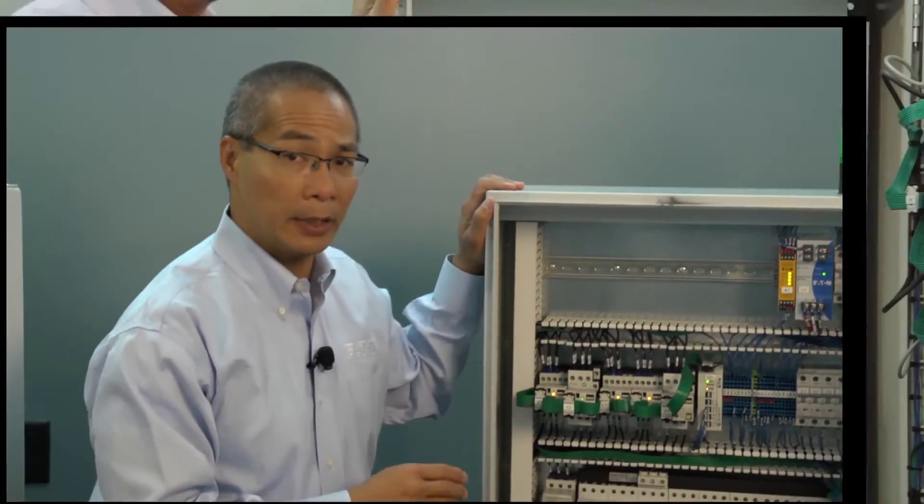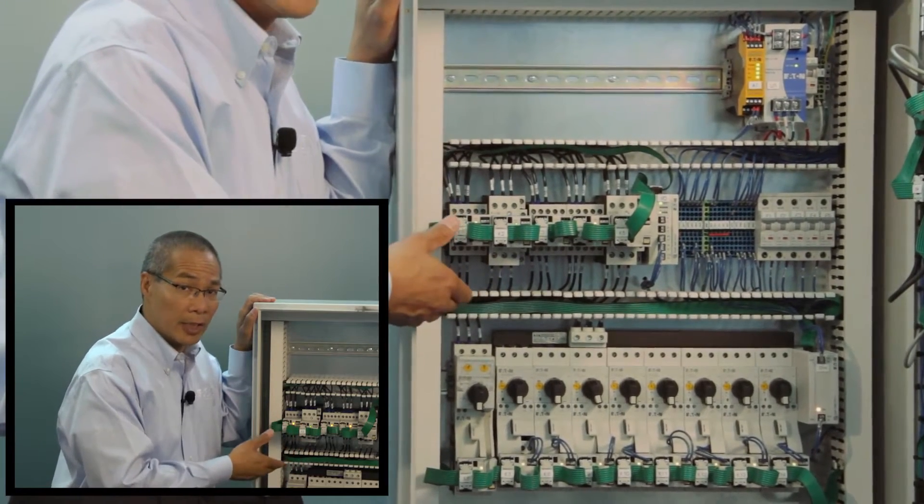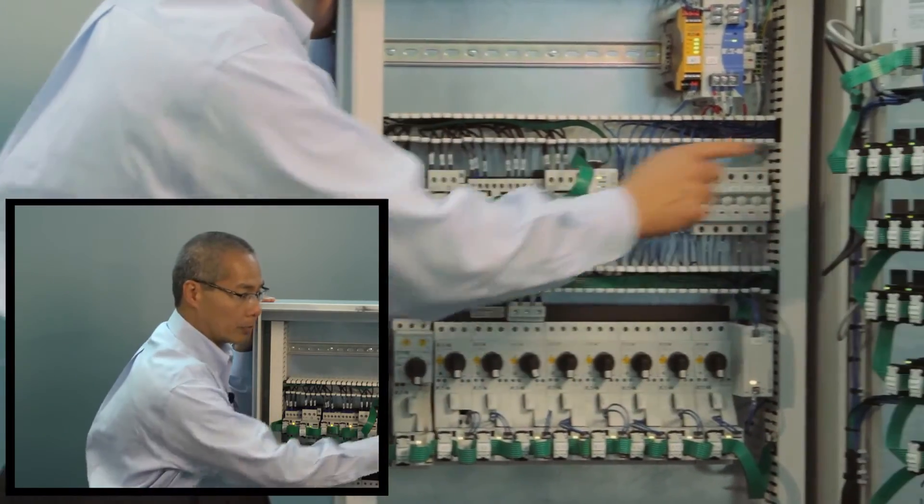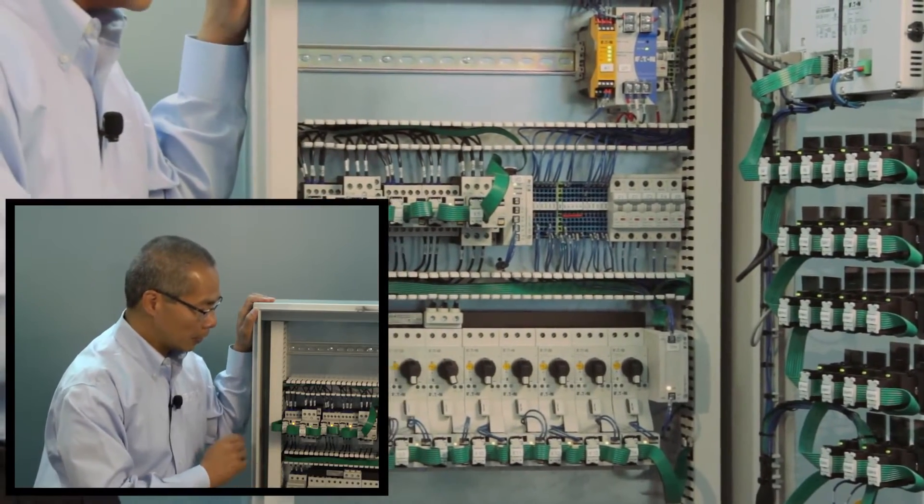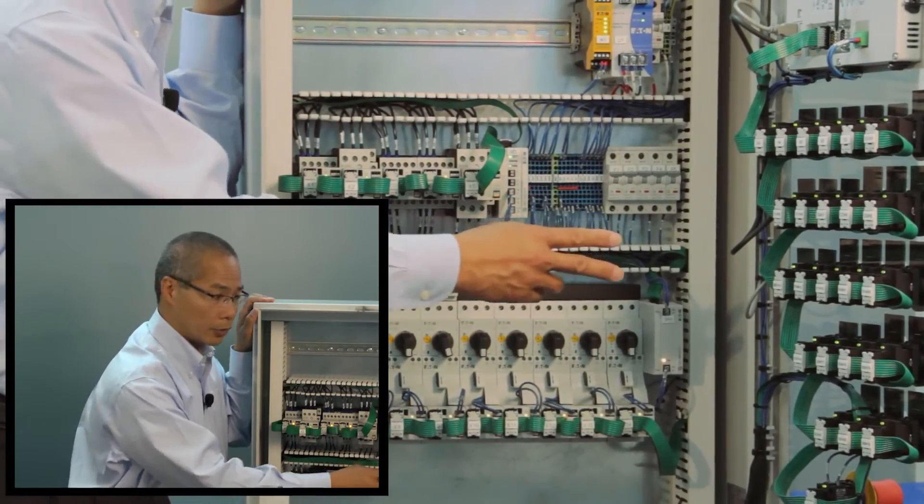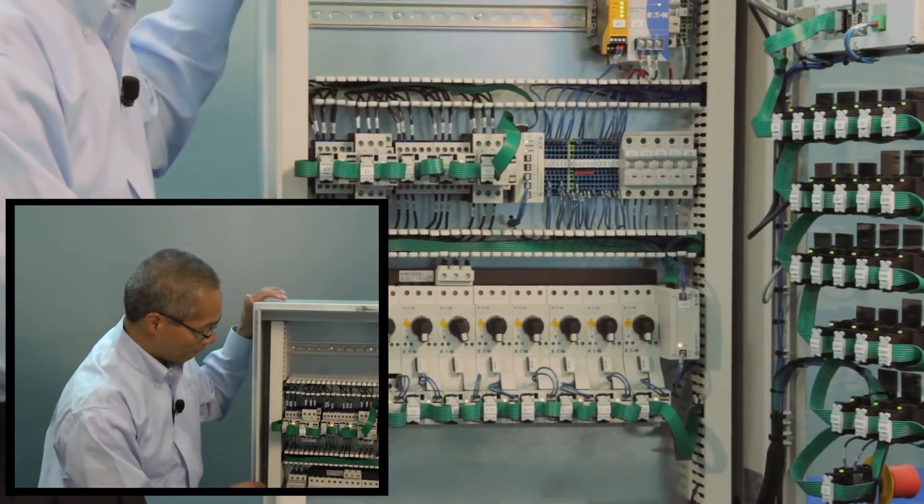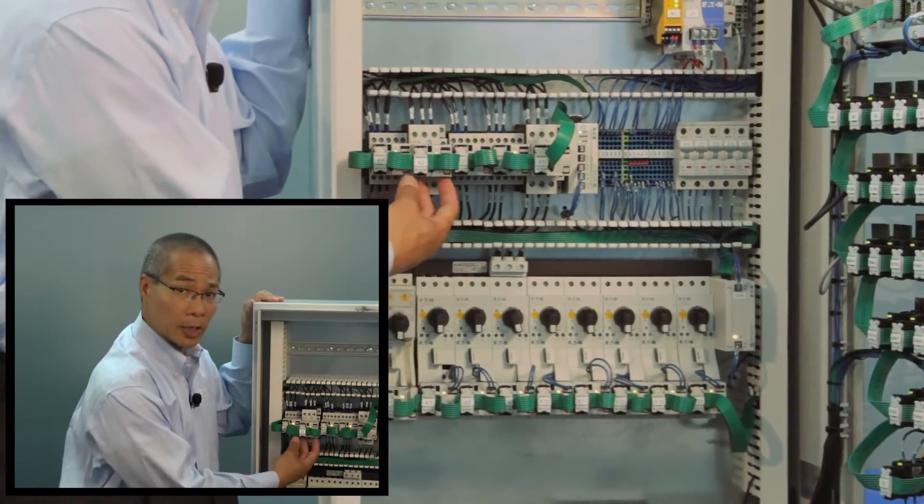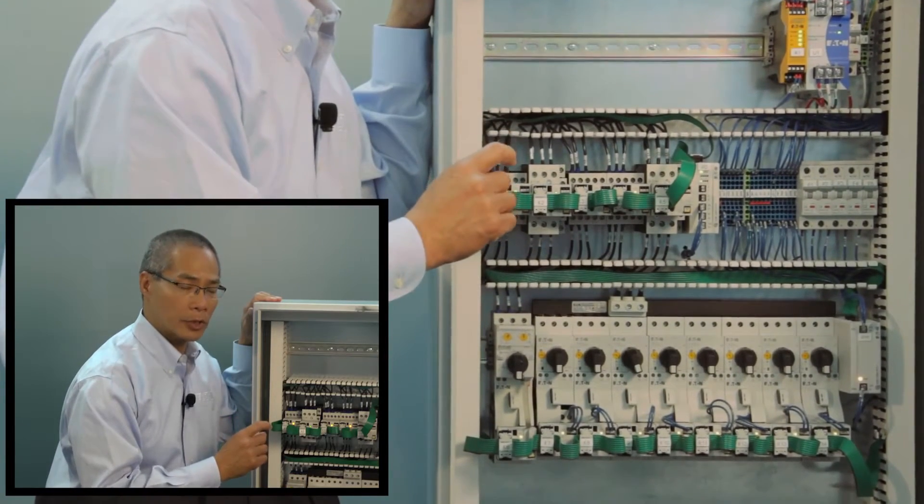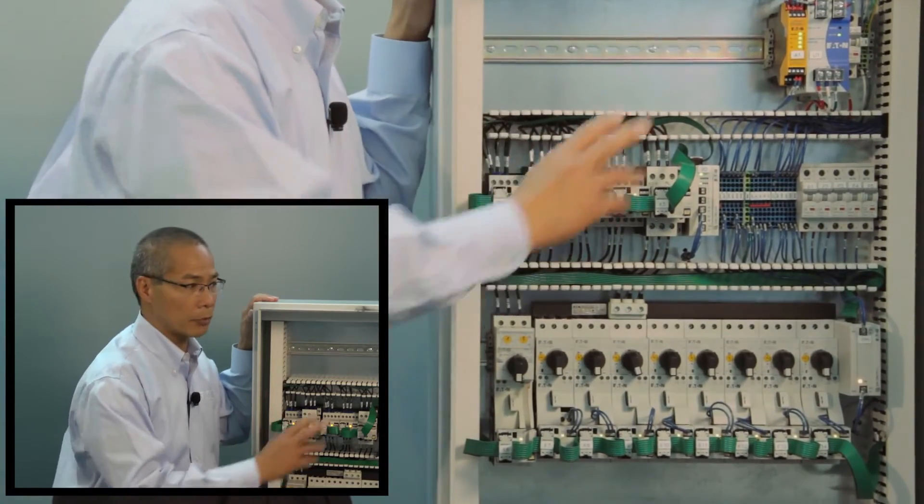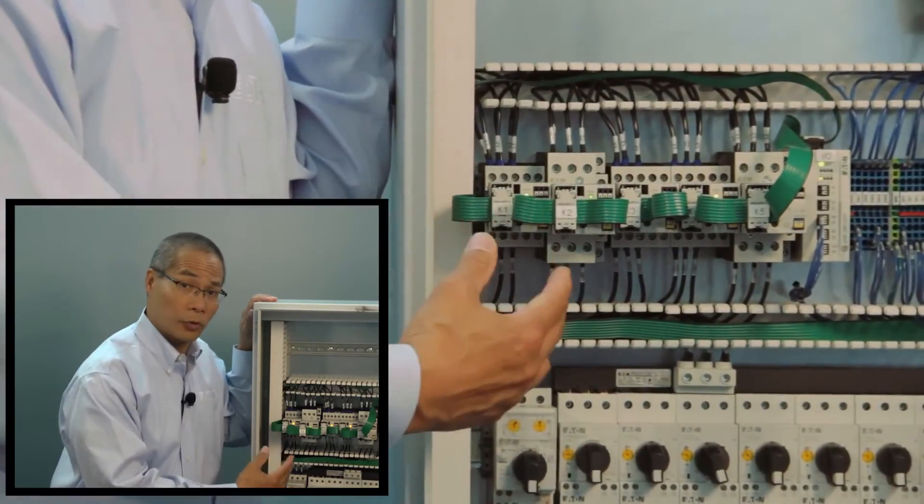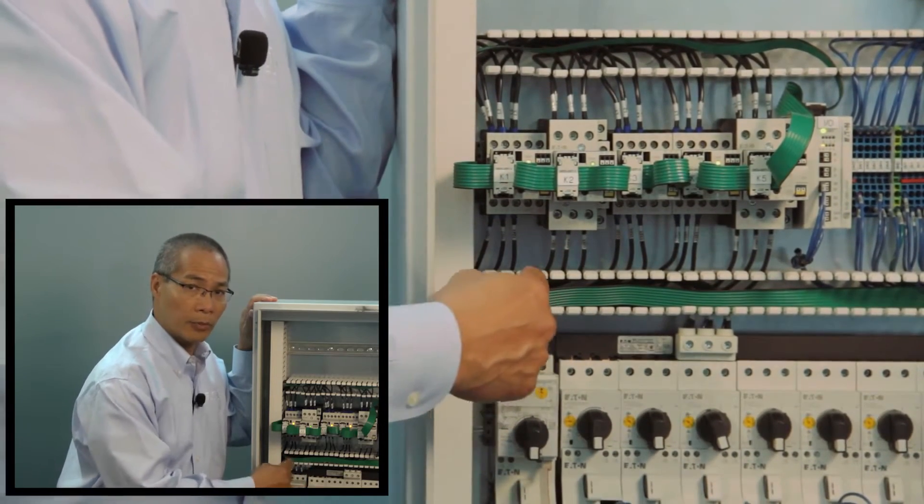As you can see, what SmartWire DT does is really essentially standardize the connections that it makes to all your components. We're using the same connector, whether it's attached to the contactor module or a push-button module. The other thing to notice is we're using still standard control components. The motor contactors that you see here and the pilot light devices on the door are all standard components. What's different is the module that sits on top of the contactor and the module that plugs into the back of the push-button unit. Inside those modules, we have a smart chip that allows us to make these components smart enough to talk directly to the HMI PLC. Essentially, that gives us basically a distributed I/O point down to each component device.